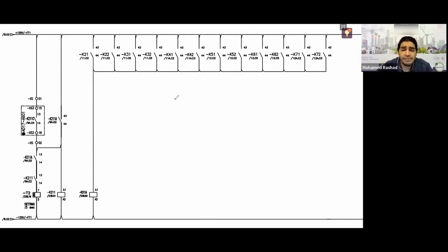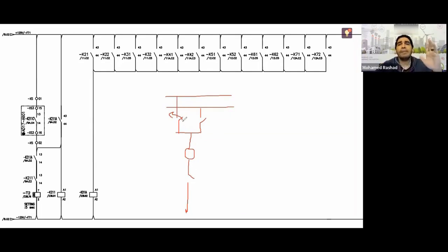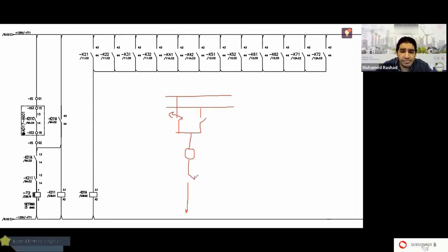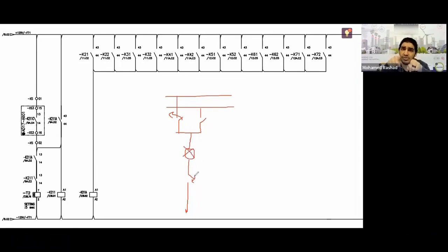Okay, now I have a double bus here, and here's a knife switch here, and another knife switch here, and here's my circuit breaker, and there's another knife switch here. All right, good. Now, I've given the close command to this disconnector. Let me give you an easy example. This disconnector has closed. As it was closing, what if it hasn't fully closed yet? It's almost there, but there's still a gap.